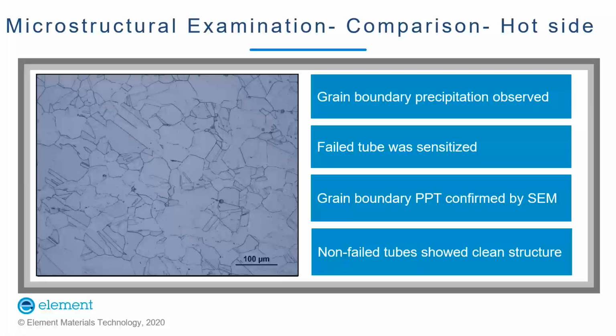This suggests that, for some reason, the failed tube was subjected to an improper manufacturing process, most likely improper annealing temperature or cooling rate during fabrication. This study also explains why other tubes didn't fail and only one tube failed and cracked during operation.